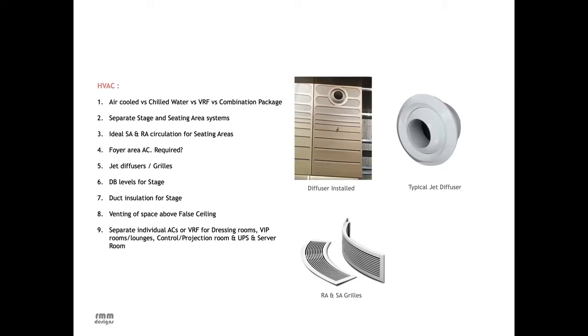The reason why air cooled is preferred is because auditoriums are typically not used as often as some of the other areas. Like, you may have offices, you may have residences, other similar structure. Auditoriums, especially large auditoriums, are not used as often. So if you are going to use a large auditorium in an institute for, say, 4 or maximum 5 times in a month, then for the rest of the days when the system is not used, it starts corroding very fast. So that is why chilled water system is not preferred. You then go in for an air cooled system. For smaller auditoriums, you can have VRF also. Combination package, what we already spoke about.